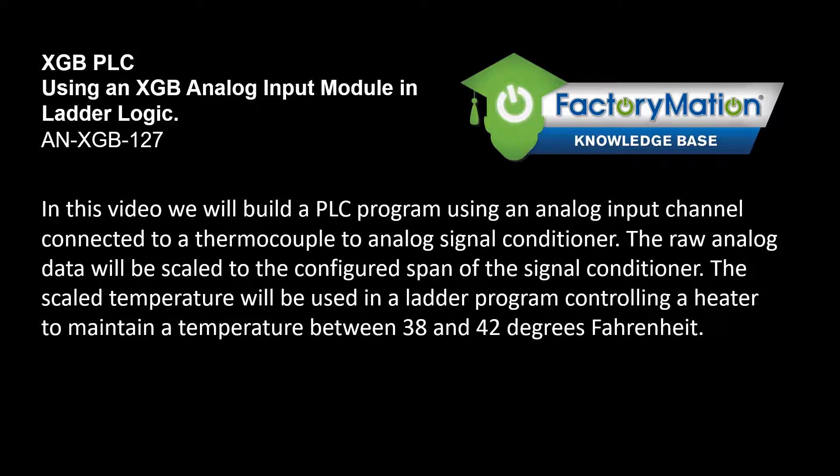In this video we will build a PLC program using an analog input channel connected to a thermocouple to analog signal conditioner. The raw analog data will be scaled to the configured span of the signal conditioner. The scaled temperature will be used in a ladder program controlling a heater to maintain a temperature between 38 and 42 degrees Fahrenheit.